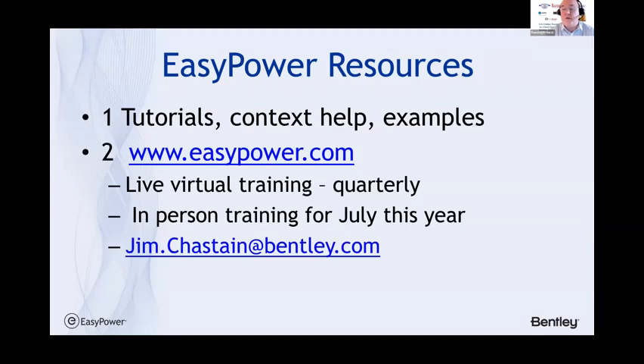Okay. Can you please discuss arc flash on DC systems such as batteries, inverter-based systems? The answer is yes. 1584 does not cover arc flash model for DC. EasyPower uses a method called max power method, which has been presented in several papers in IEEE presentations. More recently, it's been discussed that the max power method is a little too conservative. And so there's been papers at several conferences I've attended that suggest there's a less conservative methodology coming out. And we should see announcements on that during this coming year. And EasyPower will basically follow that based upon the consensus.